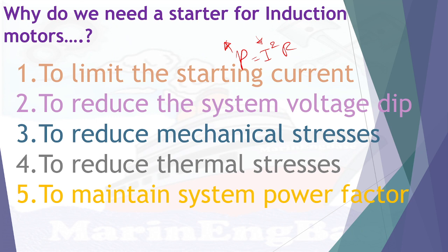The fifth reason is to maintain the system power factor. During motor starting, its power factor is very low. As I explained in my previous video, the motor power factor increases as it picks up speed. If the motor operates at low power factor, that directly affects your system's electrical supply and its power factor will also fall. So to maintain system power factor, we can also use a motor starter.